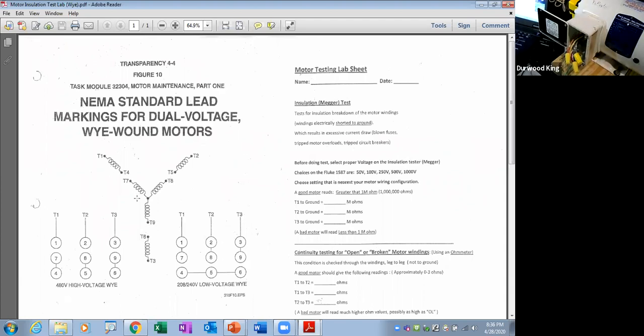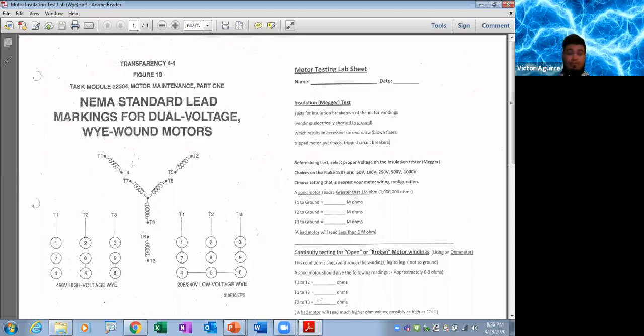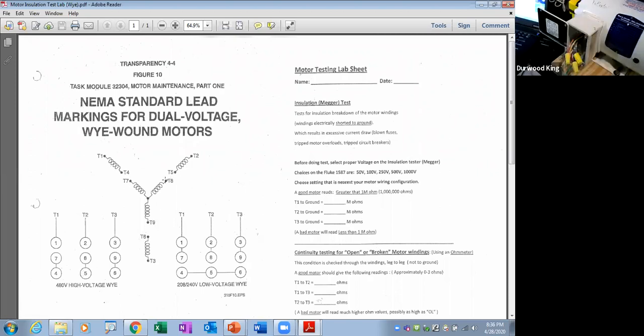Now take a look here. If you wire this motor up high voltage, guys, look at here. You're hooking 4 and 7 together with a wire nut. Look at that. See that right there? Yep. You're tying 4 and 7 together, and then 5 and 8 down here. You got 5 and 8 together. See that? That's a wire nut there. And then 6 and 9. So you got a wire nut here, here, and here, and that puts all the windings in series. It puts them in series.